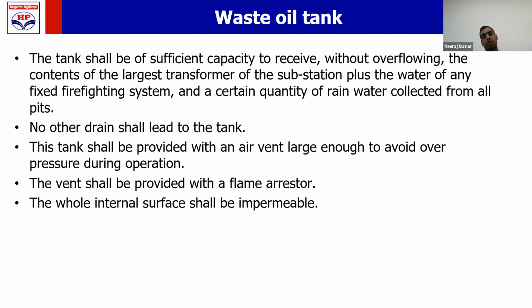The internal surface of the tank shall be impermeable. The entire purpose of this exercise of putting a waste oil tank and oil containing pit was that your oil should not reach the water stratum. So obviously your tank should be of impermeable material, generally concrete का बनाते.